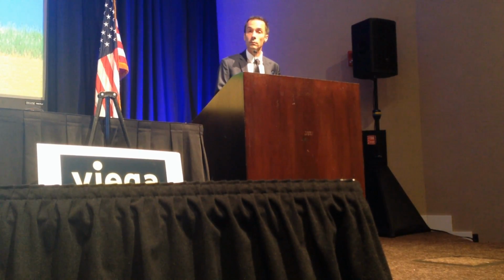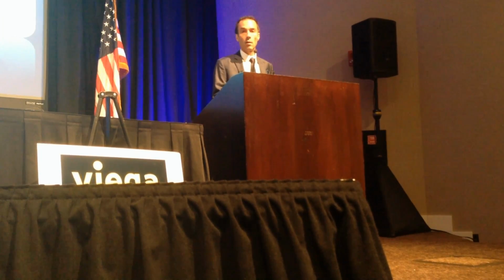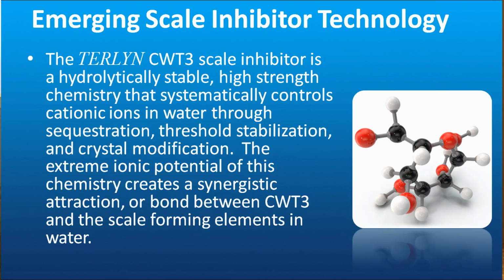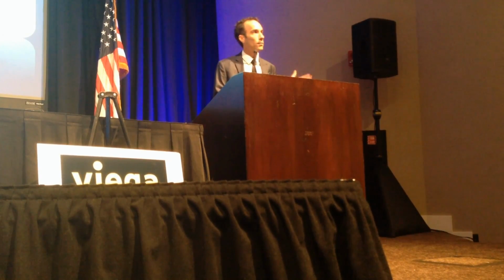So if we can use the existing equipment and reduce the amount of wastewater, then it's a viable solution. The emerging scale inhibitor technology I'm going to present today, the TERLYN CWT3 scale inhibitor, is a hydrolytically stable, high-strength chemistry that systematically controls cationic ions in water through sequestration, threshold stabilization, and crystal modification. The extreme ionic potential of this chemistry creates a synergistic attraction, or bond, between the CWT3 and the scale-forming elements in the water. And I know that's a mouthful.